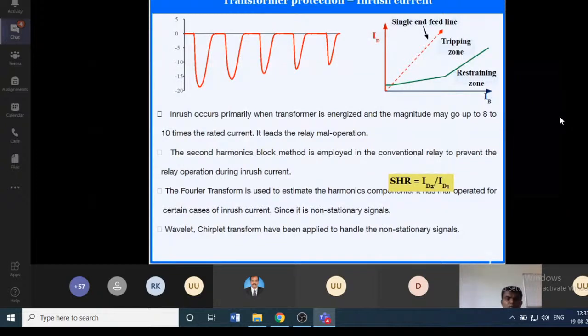The Fourier transform used in the conventional relay has maloperated in certain cases, because it cannot be applied to non-stationary signals. When you have high transient signals in the power system, that is a non-stationary signal, right? That will lead to maloperation in the case of the Fourier transform. To avoid this, the wavelet transform and the S-transform have been applied to handle these non-stationary signals.